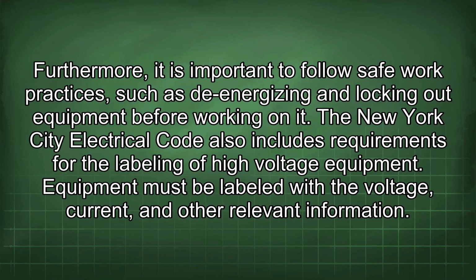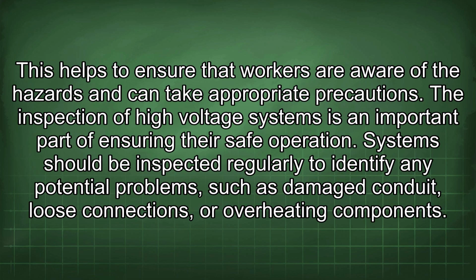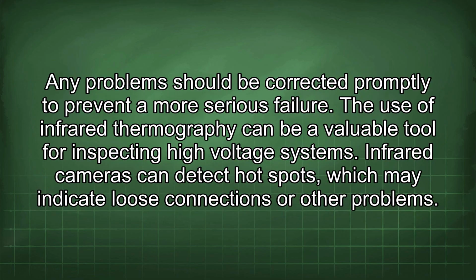The New York City Electrical Code also includes requirements for the labeling of high-voltage equipment. Equipment must be labeled with the voltage, current, and other relevant information. This helps to ensure that workers are aware of the hazards and can take appropriate precautions. The inspection of high-voltage systems is an important part of ensuring their safe operation. Systems should be inspected regularly to identify any potential problems, such as damaged conduit, loose connections, or overheating components. Any problem should be corrected promptly to prevent a more serious failure.